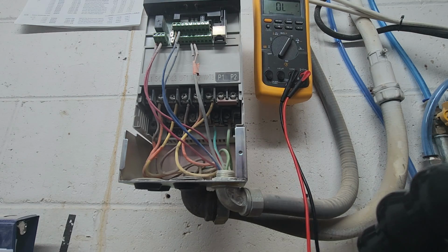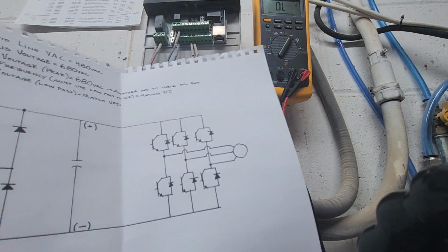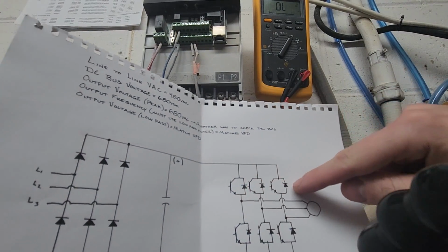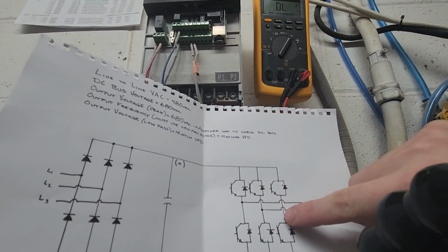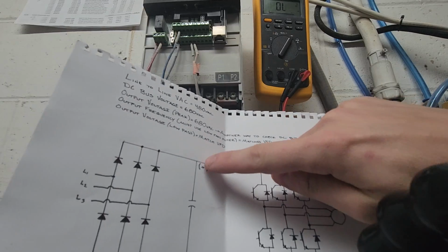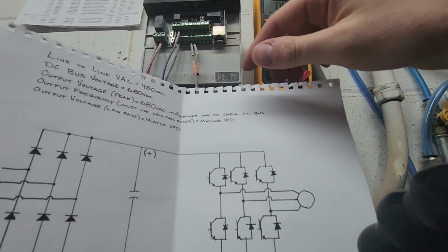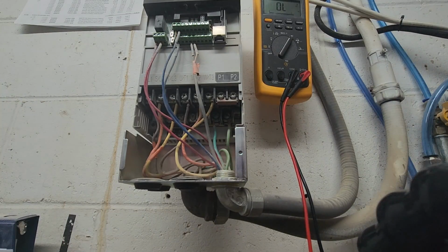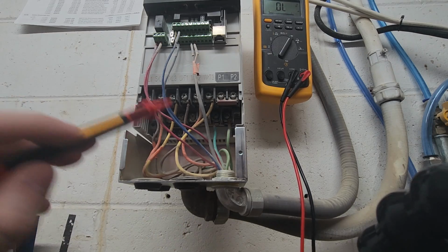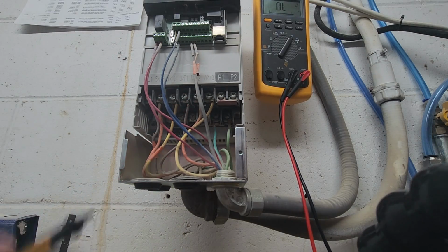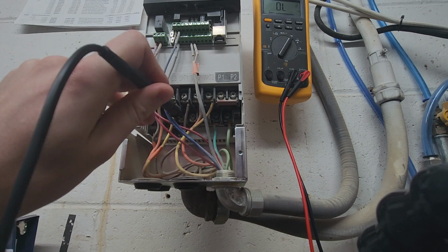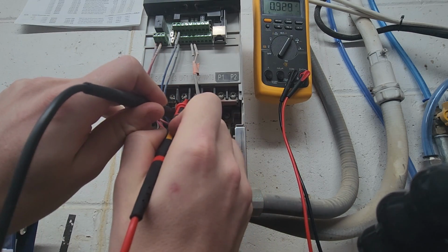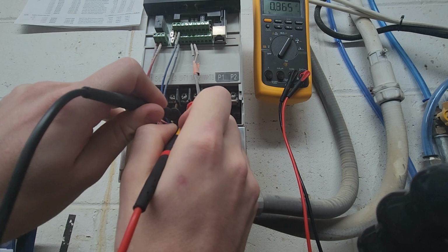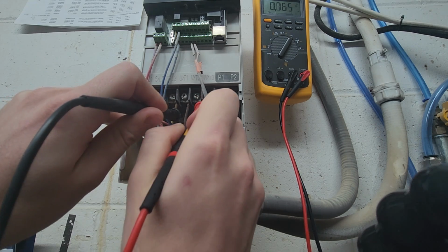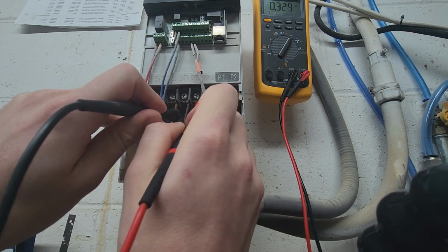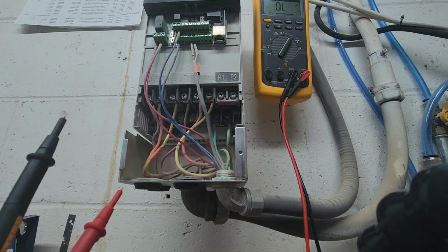Next we'll check our flyback diodes. We'll check these top 3 first, so we'll put our positive lead on our 3 outputs, and we'll put our negative lead on our DC bus positive, and we should get a similar reading. So negative on your DC bus positive, and then your 3 outputs, 0.32, 0.33, 0.329. That's perfect. So our diodes are working in the one direction.